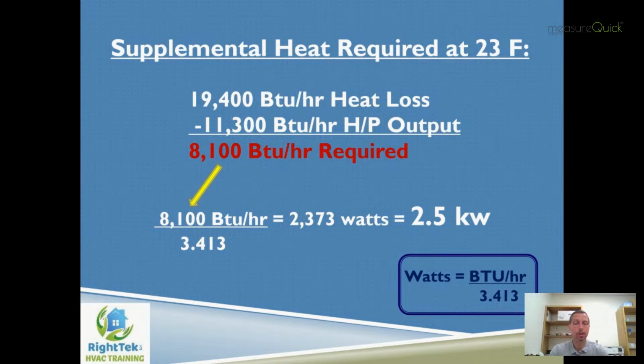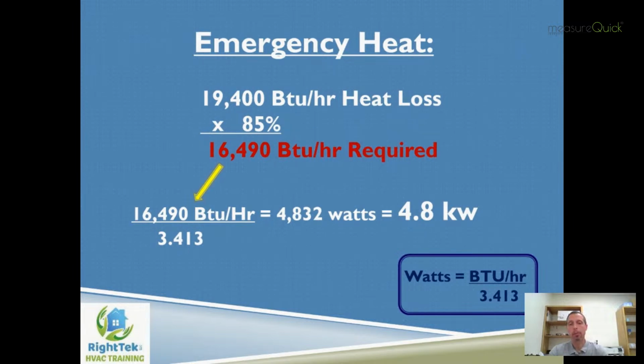Now, there's also a school of thought out there that, okay, I see what you're saying, Anthony. I can just size for the supplemental heat, but if I'm putting heat strips in here anyway, maybe I want to also consider being able to provide some degree of emergency heat should something break down, should something go wrong in the middle of a cold snap and I can't get a tech out there immediately. I can try to maybe keep that customer reasonably warm. So again, same scenario as always. Manual S recommends not sizing emergency heat for more than 85%.